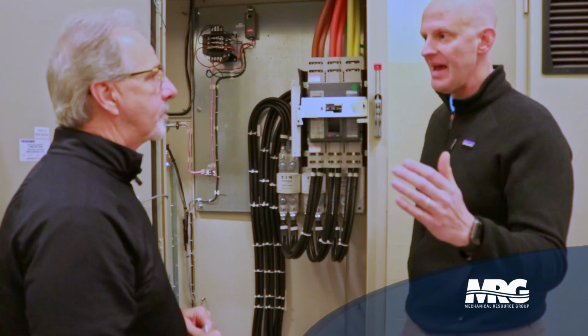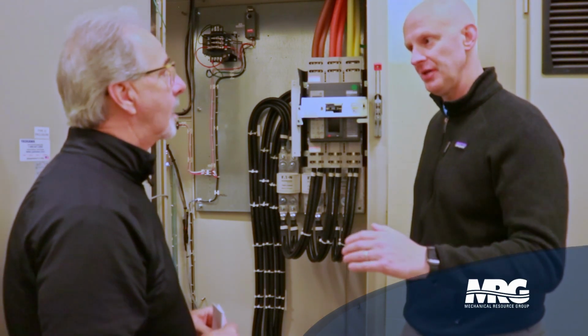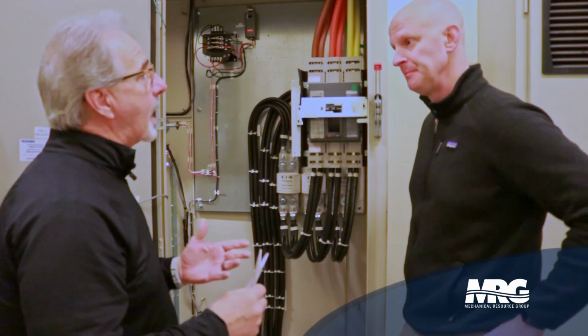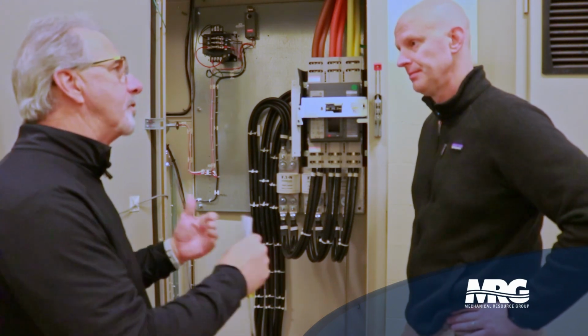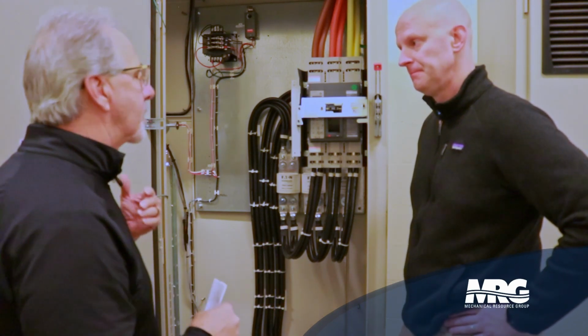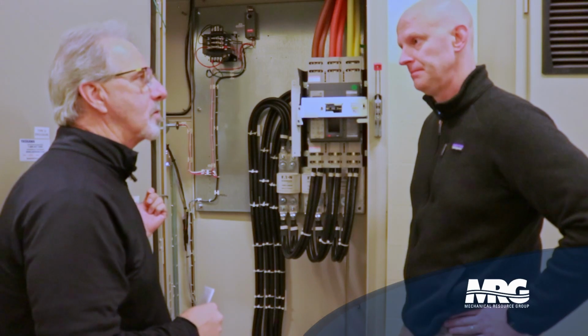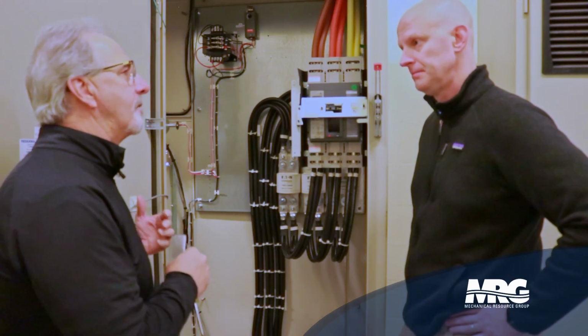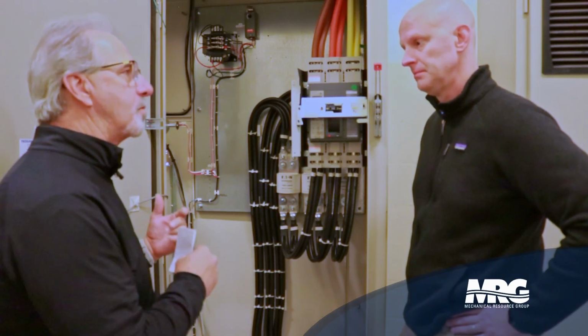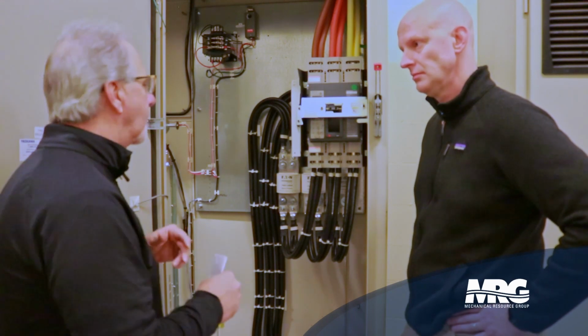Correct. And does that help us size the filters? Can the filter be sized smaller? Yes, we were able to size the filter smaller because it was kind of a trade-off. Yeah. We really wanted to go to the matrix drive that Yaskawa offers, but they didn't have it in the horsepower that we required. So that's when we opted for the GA800 multi-pulse input diodes with the reactor.